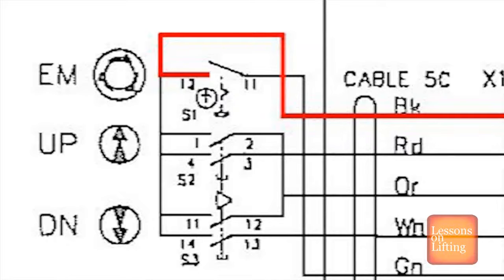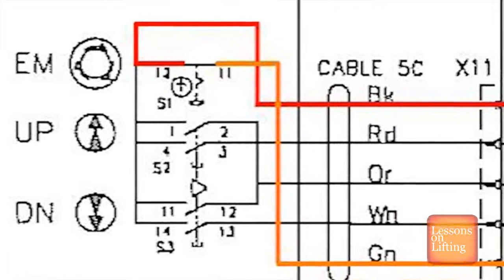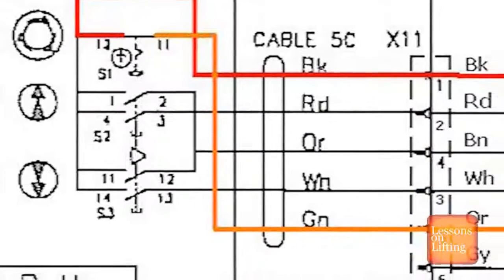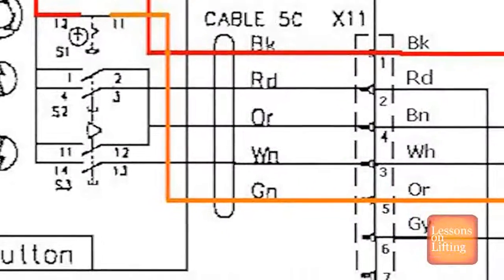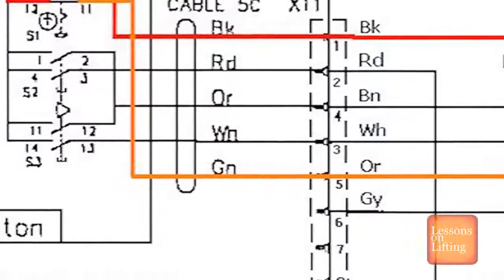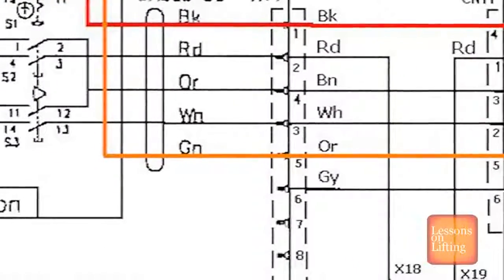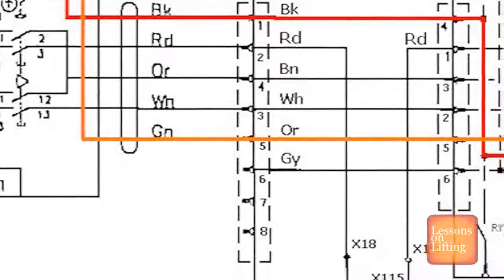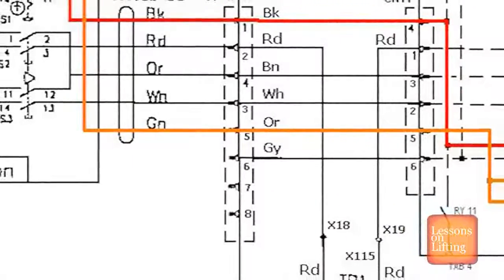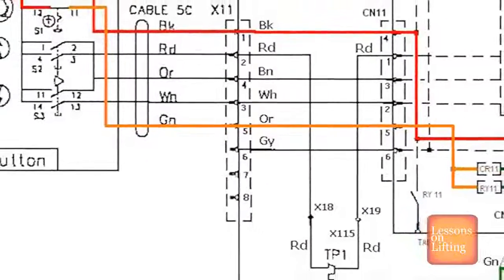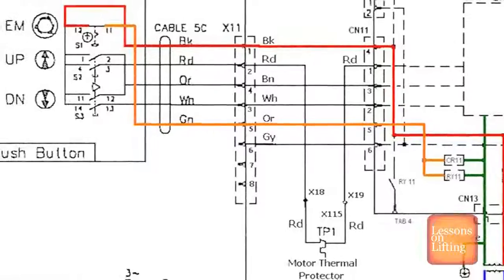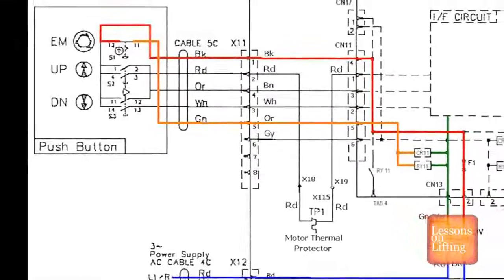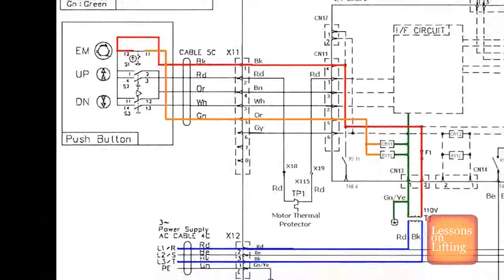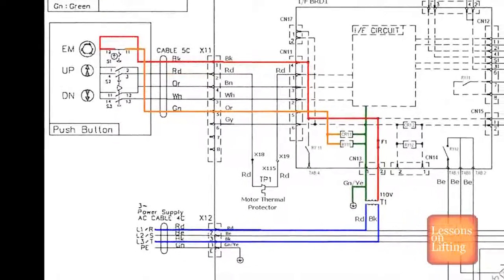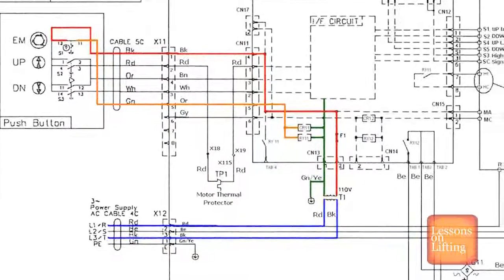Inside the pendant, if the e-stop button has been released, it closes the switch, and voltage then goes on a green wire back to the 8P plug. Many people call and say, hey, where's this? You got a short in your pendant. You got power going to this green wire. The green wire is not a ground in the standard ER2, MR2 pendant.